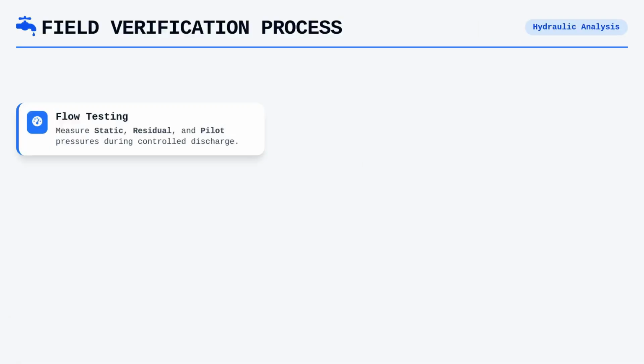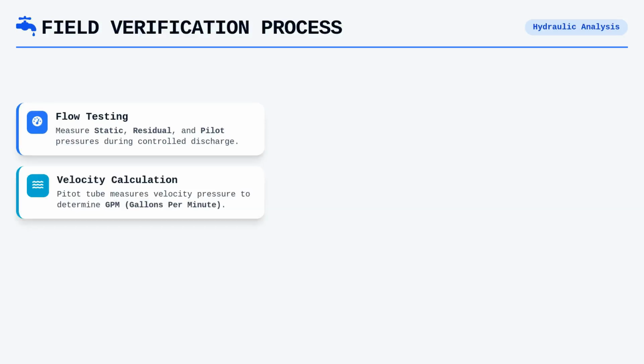Field verification usually involves flow testing, where we measure the static pressure, the residual pressure, and the pitot pressure during a controlled discharge from a hydrant. The pitot tube, when inserted into the stream of the flowing water, measures the velocity pressure, which allows us to calculate the actual flow in gallons per minute.